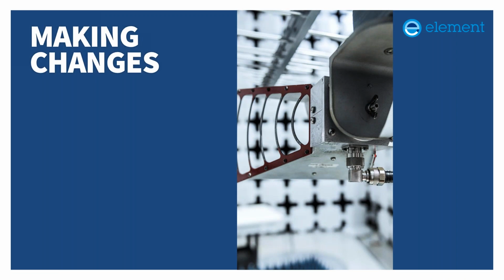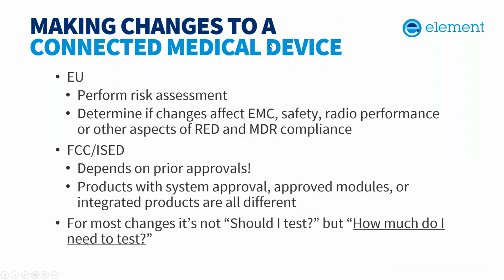Okay, so you've got a medical device you released to the market, think everything's good, and then something comes along and you need to make a change. What do you need to do? So unfortunately, the classic answer, it depends. It depends on what the change is and depends on the product. So first off, take a look at and do an EMC risk assessment. How does this change affect the medical device functions? And will this affect the results for 60601?